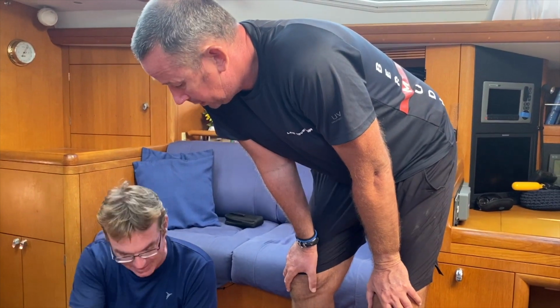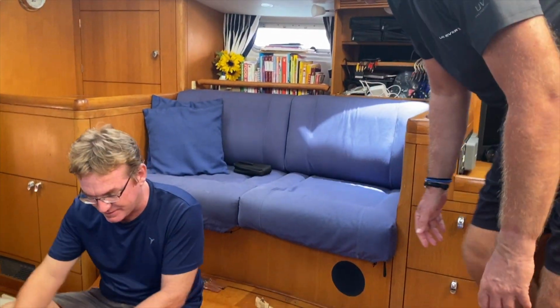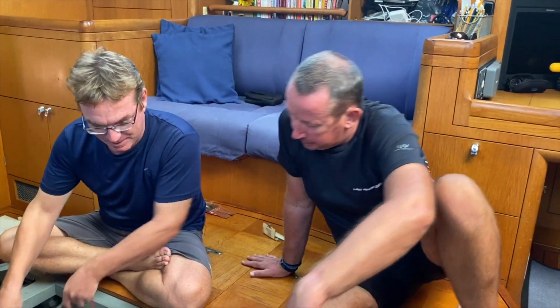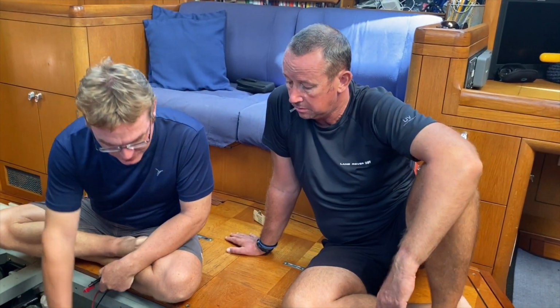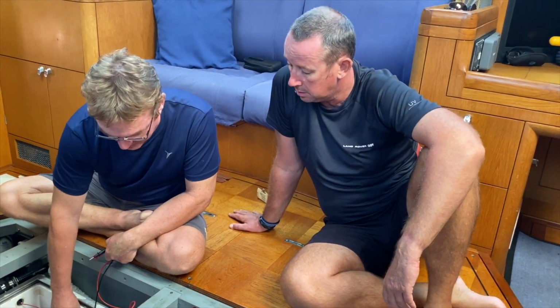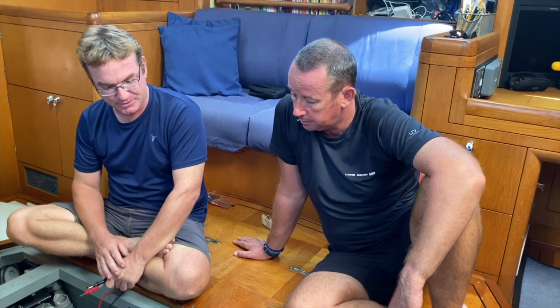You don't need to test every single battery, but it doesn't hurt to hit a couple points and test a battery here, test a battery there, because one of these connections could be a little bit corroded, so it's good to make sure they're all measuring the same.